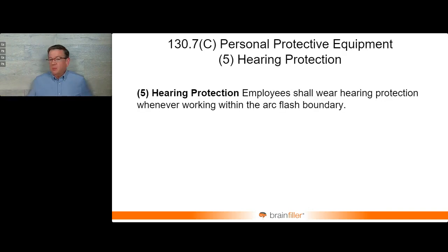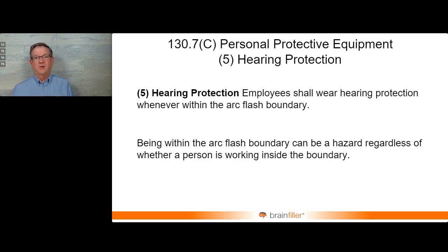Hearing protection. Hearing protection has been a requirement for some time now, but the way it was written kind of took a step back and thought, we need to think about this. The way it was written, employees shall wear hearing protection whenever working within the arc flash boundary. What if somebody's in the arc flash boundary and they're technically not working? Okay, it applies to everybody within the arc flash boundary, regardless of whether they're working or not.